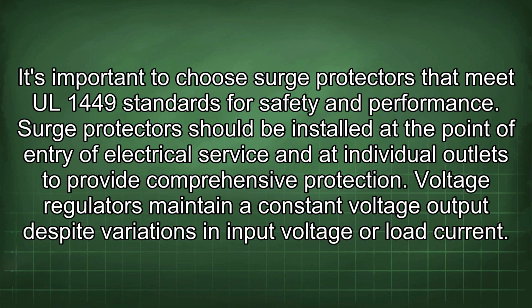It's important to choose surge protectors that meet UL 1449 standards for safety and performance. Surge protectors should be installed at the point of entry of electrical service and at individual outlets to provide comprehensive protection. Voltage regulators maintain a constant voltage output despite variations in input voltage or load current.